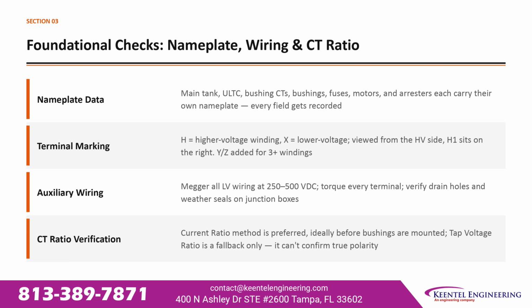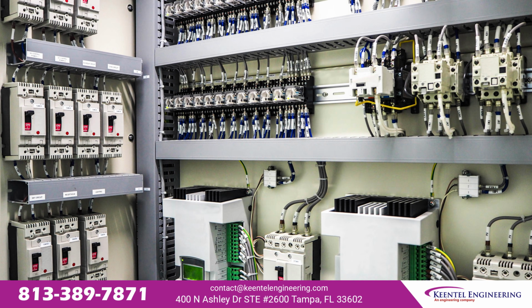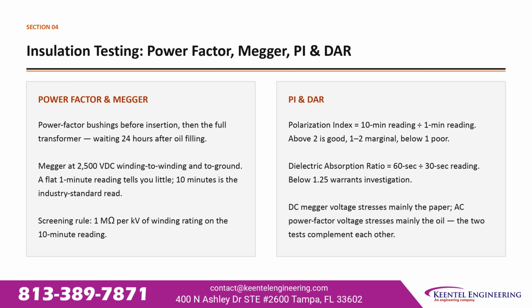For CT ratio verification, the current ratio method is preferred, ideally performed before bushings are mounted. Tap voltage ratio is a fallback only. It can't confirm true polarity. Power factor tests the bushings before insertion, then the full transformer, waiting 24 hours after oil filling before you test.